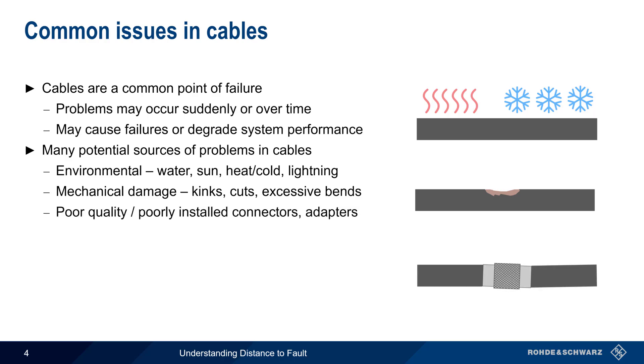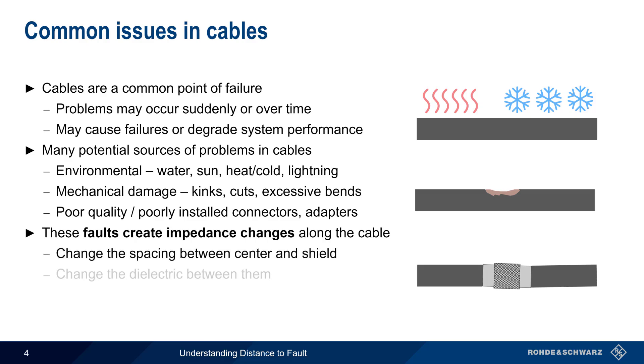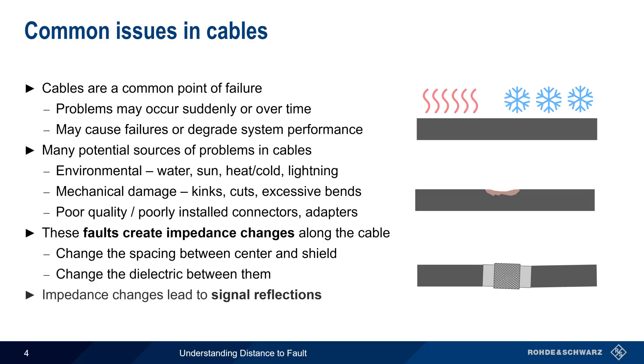Installation or materials issues are another common cause of cable problems. All of these problems, or faults, have one common characteristic: they change the impedance along the cable. Anything which changes the spacing between the center and shield, or the dielectric between them, will change the cable's impedance at that point. And these impedance changes cause signal reflections at the points where these changes occur.